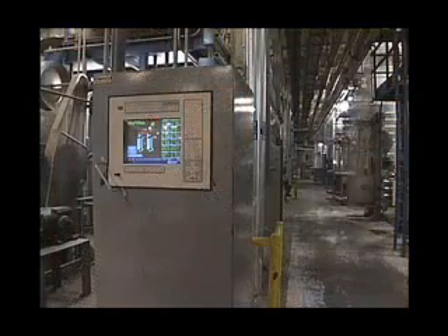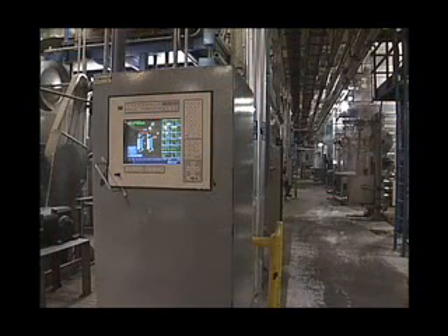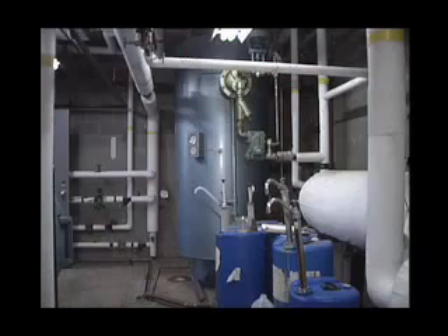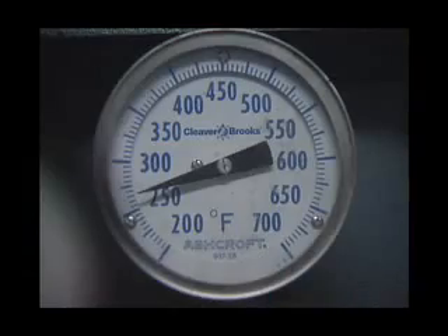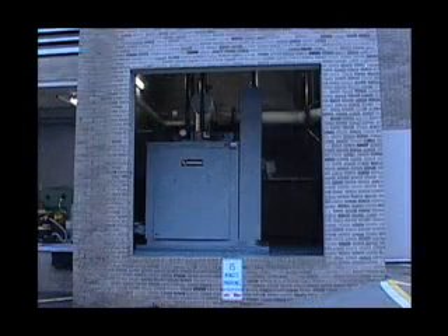The installation was fairly easy. All we needed was a small amount of floor space. We built the building and put the boiler in place, tied it in with the feed water and the steam lines, and it was ready to go. From a cold start, this electric boiler is capable of producing 90 pounds of steam within 30 minutes. A typical fuel oil boiler will take 3 to 4 hours to warm up. The equipment's operated perfectly and it's never failed us yet. I would highly recommend an electric boiler to any facility that could use additional steam plant capacity but still has limited floor space.